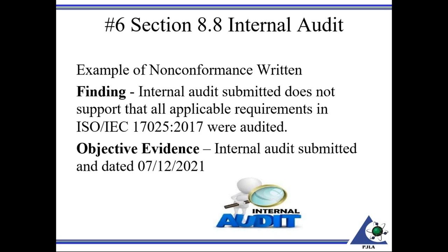Example of a non-conformance written. Internal audit submitted does not support that all the applicable requirements in 17025:2017 were audited. And the objective evidence that was reviewed was the particular internal audit that was conducted on this day.